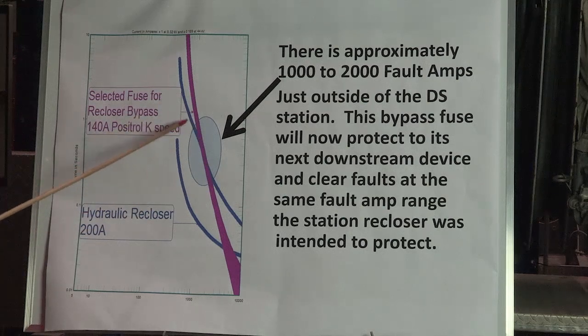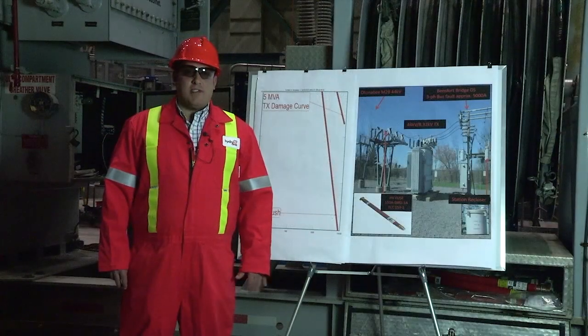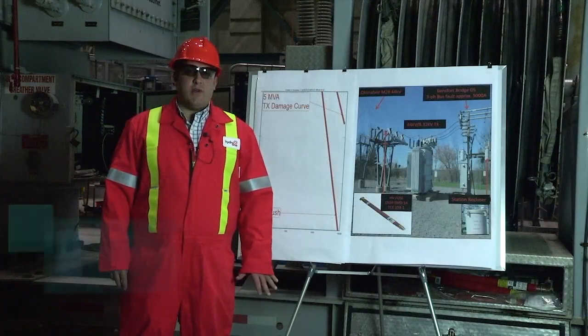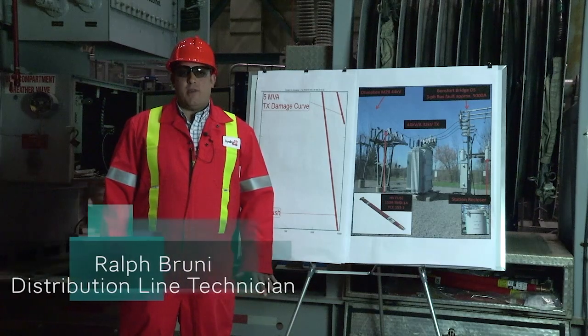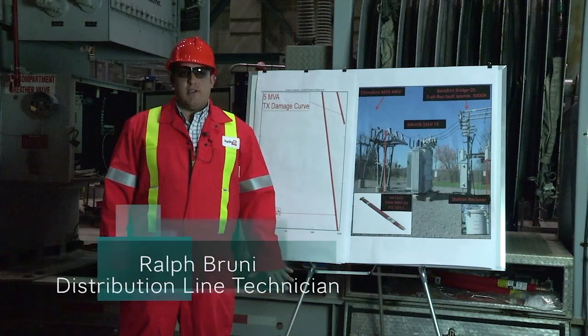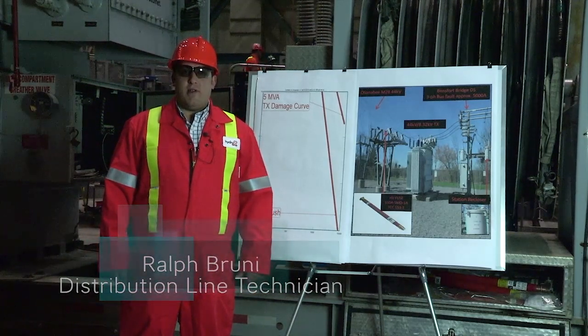Now, we're not going to be using the fast curve on the recloser. We basically want this fuse to protect everything up to its last delay curve on the recloser. So if there is a fault just outside the station between 1,000 to 2,000 fault amps, this high side fuse will protect the rest of the DS and clear that fault. So this was basically a way of showing how protection and coordination is done within Hydro One, and this is basically all done to ensure safety and reliability for our customers.